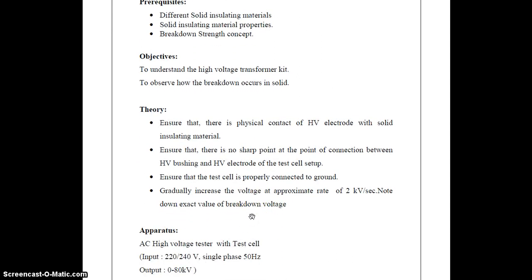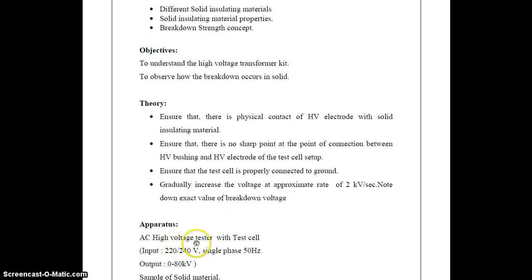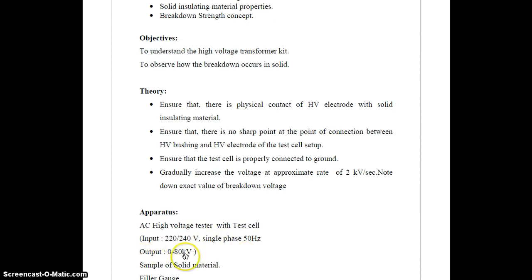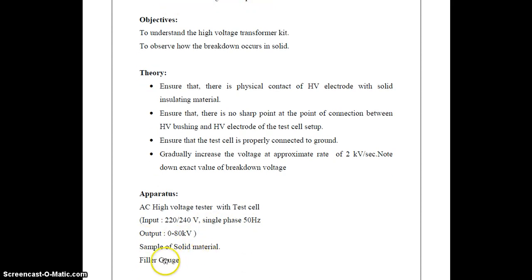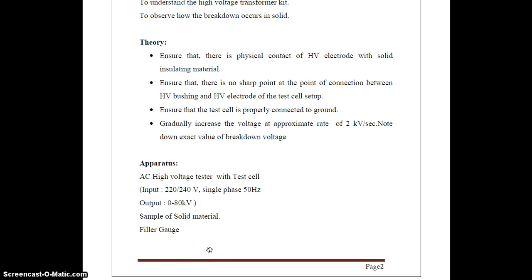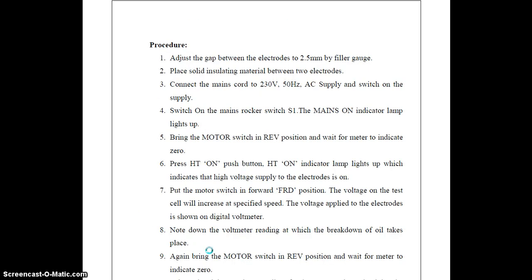Then the apparatus required: an AC high voltage tester with test cell. Input voltage is 220 volt to 240 volt, single phase 50 Hz supply. Output is 80 kilovolt. A sample solid material and a feeler gauge. Then the procedure to calculate the breakdown strength of solid insulating material. First, adjust the gap between the electrodes to 2.5 mm using the feeler gauge. Then place the solid insulating material between the two electrodes.